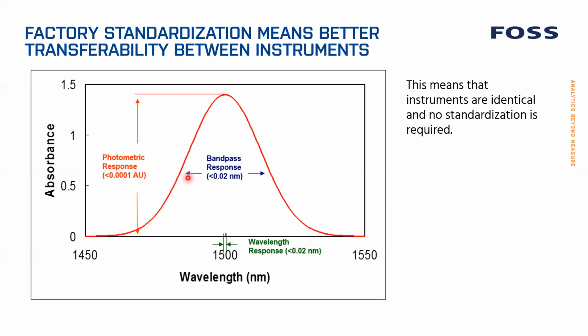The instrument itself actually has a slightly smaller band pass than we want, and then we use mathematics to widen it a little. We also look at the photometric response between the base and the peak on a couple of points to make sure that the response is accurate and within our specification. This means that instruments are identical. So if you do a calibration on one instrument, you can move it to a second instrument without doing anything and get the same result.